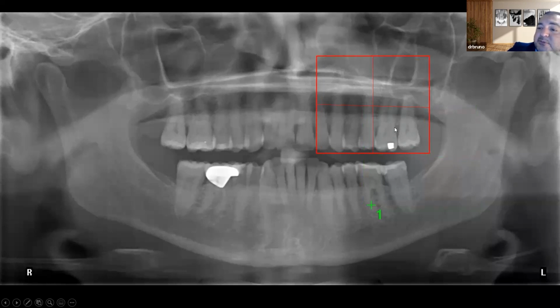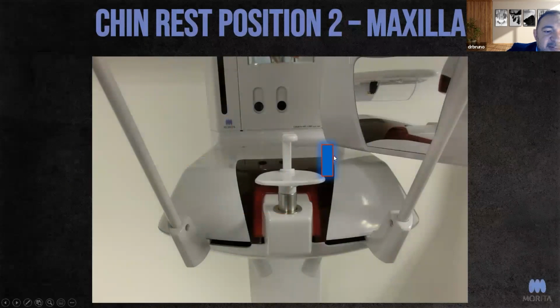So if you have problems with the box turning red for the maxilla, that is because your chin rest is too high, and therefore you can't image this properly. So every time you do a mandibular scan, I want you to use position 1. If you are going for a maxillary scan, I want you to go for position 2.